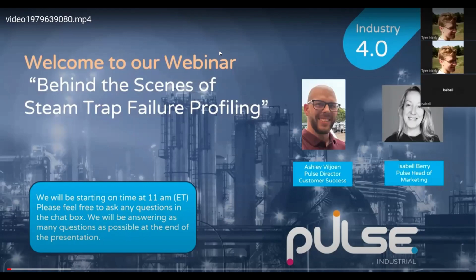When we then come on site, obviously we earmark those traps. We work with the customer to say, okay, does this make sense? Customer gives us the thumbs up, we're good to go. We then come to those particular traps. Let's say if it's 20, 30, 40 traps or whatever it is, we complete a manual audit on site. So manual audit tells us, yes, this trap is working. And then we do the installation of the sensor onto the trap.